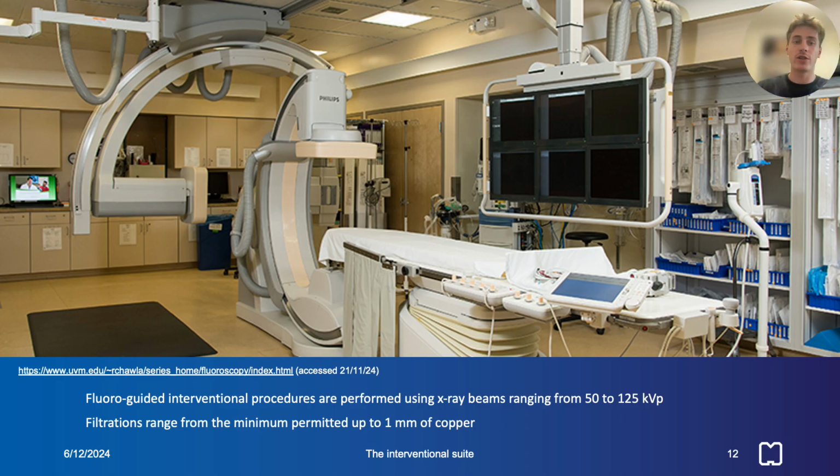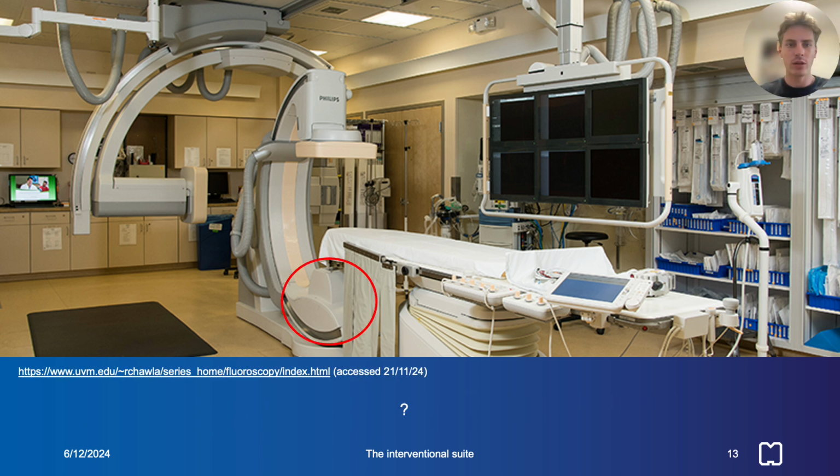Fluoroscopically guided interventional procedures are performed using X-ray beams with energies ranging from 50 to 125 kVp, X-ray tube peak voltage. Filtrations range from the minimum permitted up to 1 millimeter of copper. This image shows the interventional suite.